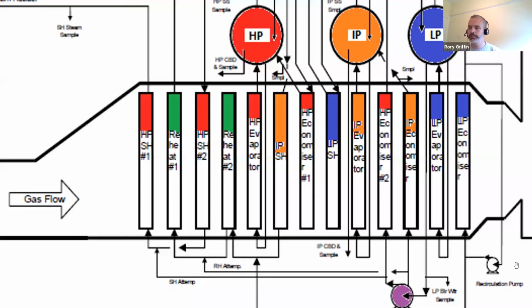So as the condensate comes from the extraction pump, it'll go up through the low pressure economizers. So if you think back to the graph in the previous slide, we're coming up the sensible heat section, and it'll come up top and go through a deaerator, which will attempt to take out any dissolved oxygen in the feed water. From here, it actually splits. The total flow rate per hour at high output is 440 tons per hour. 40 tons of condensate feed water remains in the LP boiler circuit. 400 tons will feed down to the boiler feed pumps.